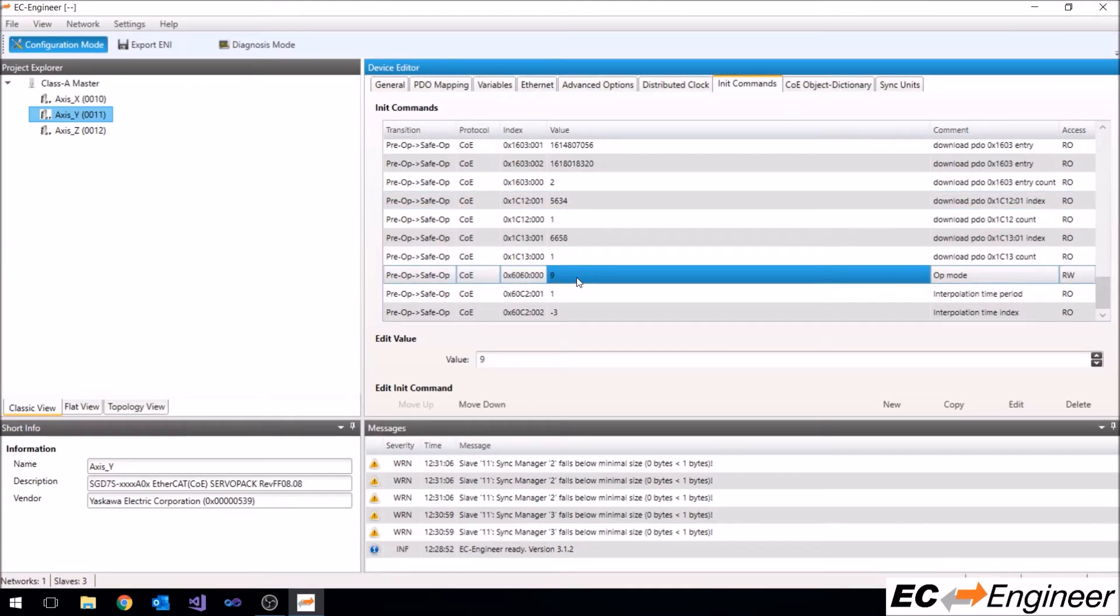Here we are changing the op mode from 8 to 9, which sets the drive to cyclic synchronous velocity mode.